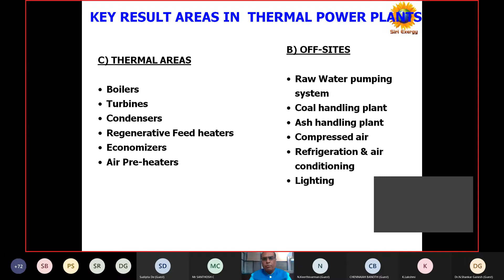So we will do further analysis on key result areas. We call them key result areas, where you can do some analysis and tell my client, whoever be my client, what actually they have to do to improve their performance. Like FD fan, that supplies our combustion air, ID fans, then to exhaust whatever flue gas is generated. Then boiler feed water pumps, as I told, boiler feed water pumps is the major load. Their consumption is somewhere around more than 30% of the auxiliary consumption, only BFPs. So there is a huge, even if you improve 1 or 2% of BFP performance, because each boiler feed pump motor will be somewhere around 3.5 megawatt.